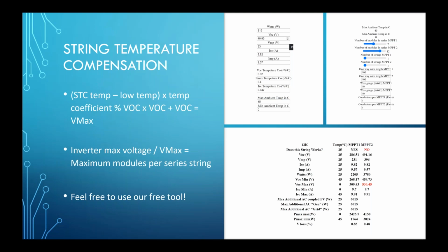Then you come to this tool right here, and this tool is for the temperature correction part. It's a string temperature compensation tool. This tool is on our website. It's for installers or homeowners that maybe are going to do their own system. You literally enter these inputs from the data sheet of the panel, and you go over to the strings and manipulate the strings. I want to use 8, I want to use 7, I want to use 9, I want to use 10, whatever it is. And then the output down at the bottom will tell you if it's okay or not from a stringing perspective. You can see there's 2 columns there, the yes and the no. The reason MPPT was no is because when you come to the VOC, you've got 530.45 volts open circuit. So that's going to violate the 500.